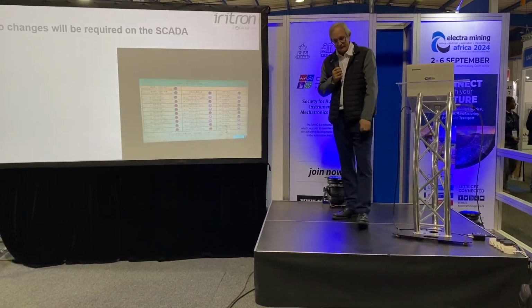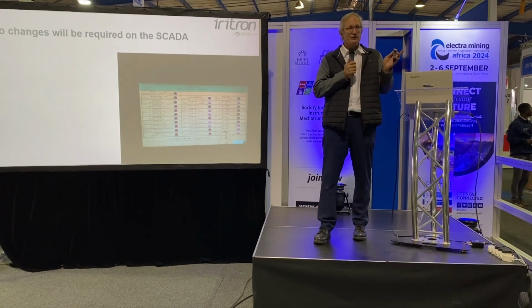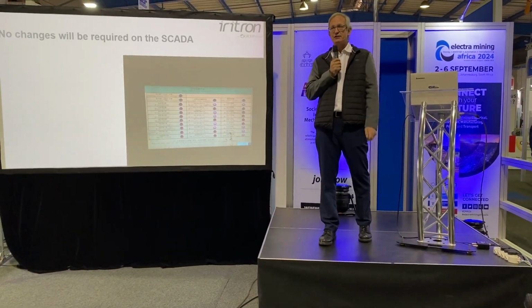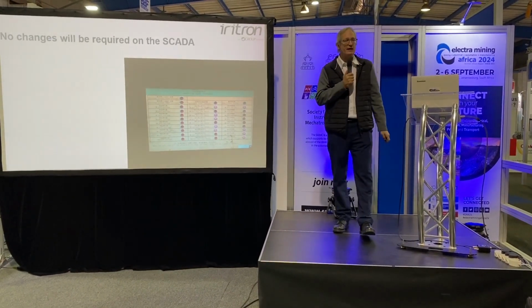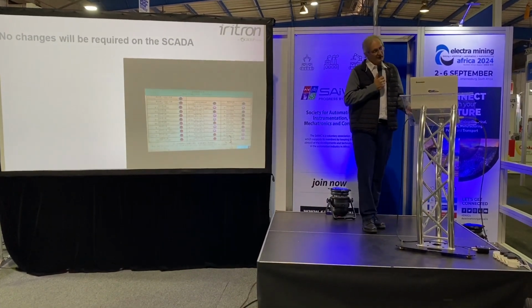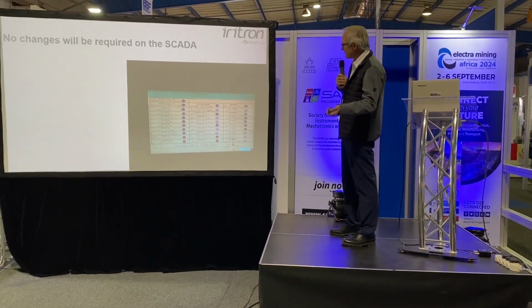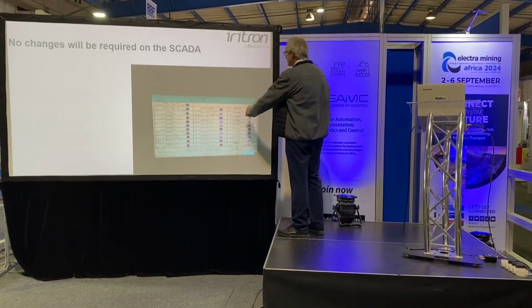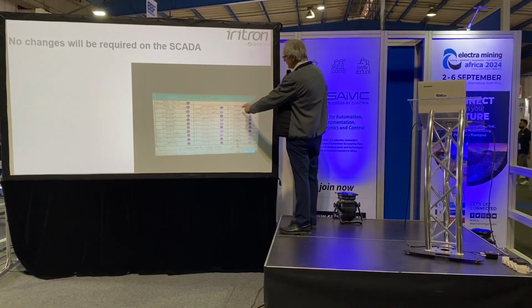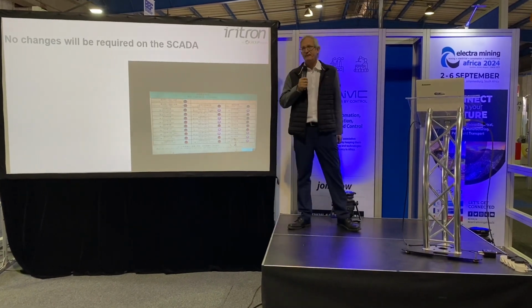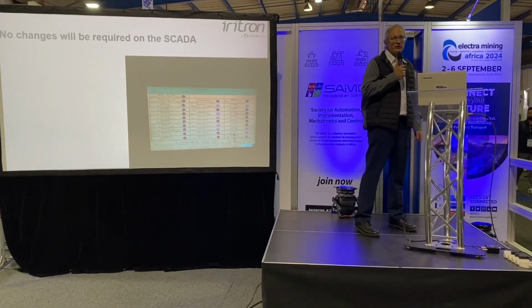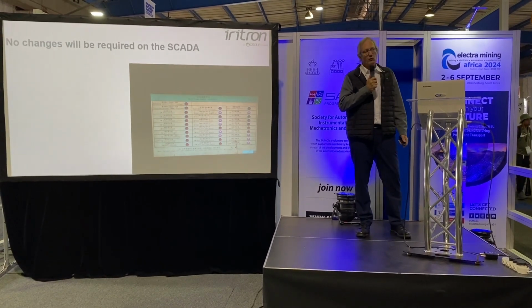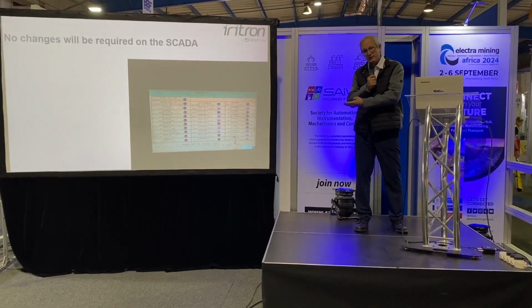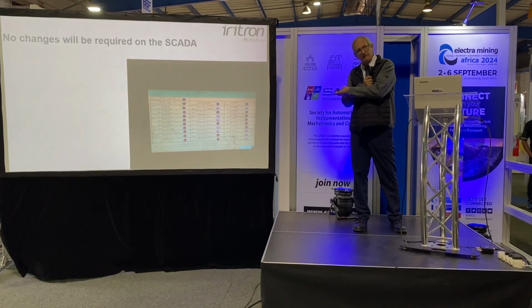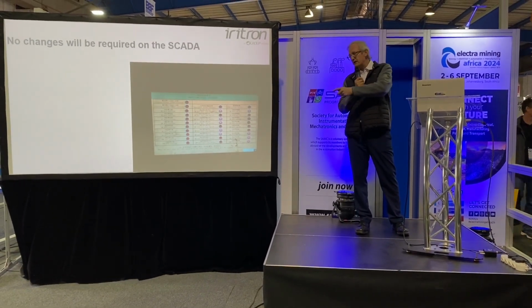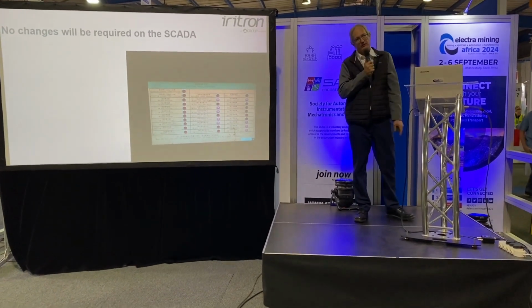The other one, we're changing out the hardware, so there'll be no changes to my SCADA system. My visualization will stay the same. If you look at the picture, you can't see, but you'll see on this picture here, if you come closer, that there's some Chinese and some English. So when you do the upgrade, you may say, well, we don't actually want to see the Chinese on the screen. That was for the Chinese that came and did the commissioning when we originally built the plant.